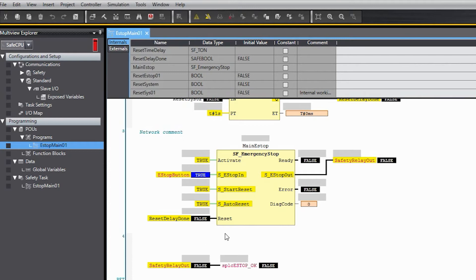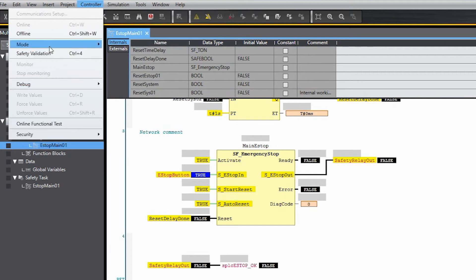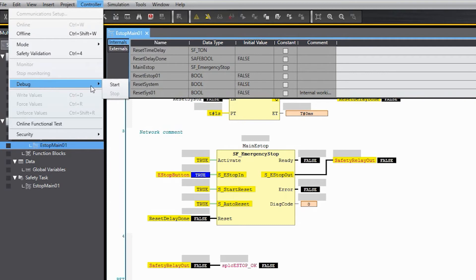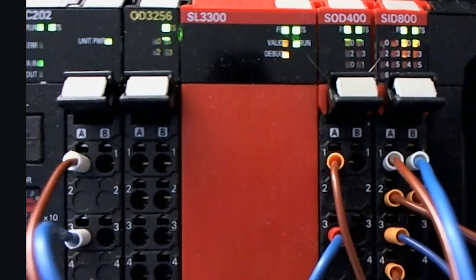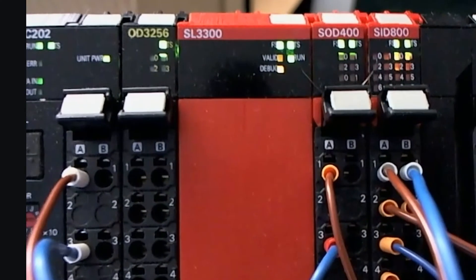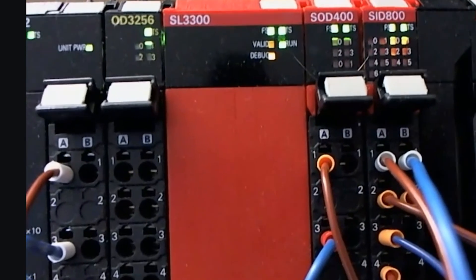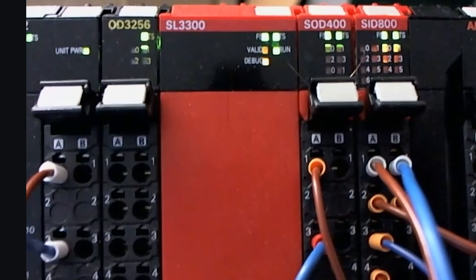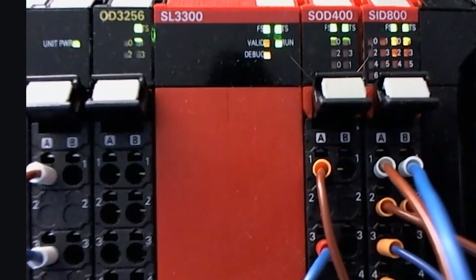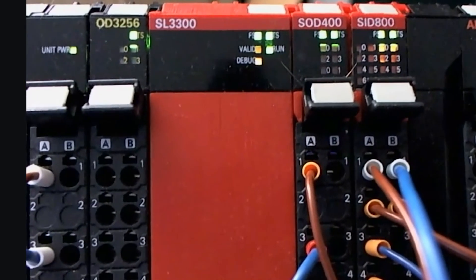So obviously the program's not running so we're going to go to the controller menu, go to debug, and then start. We already went to the mode, changed it to debug. Our only other option there is for program. So we go to the debug menu here and say start. And now right away you can see that this output is true. Also if you look at the safety CPU LEDs you can see that the debug light is on but also now the run light is on meaning that the program is being executed.